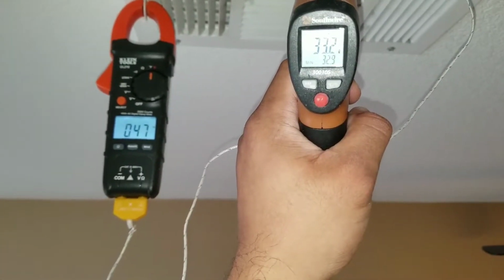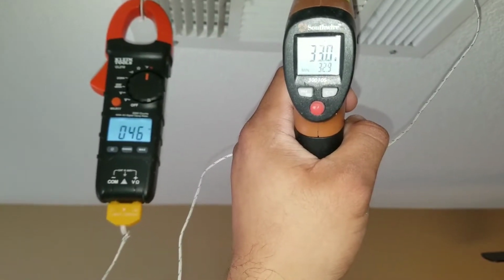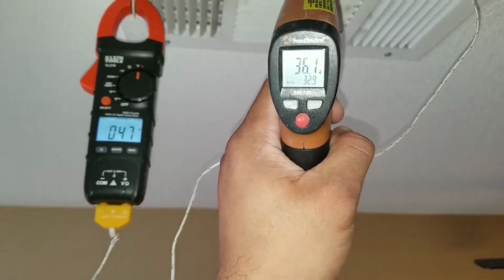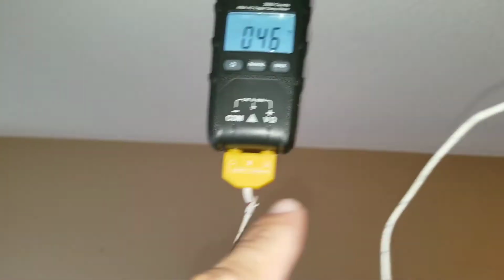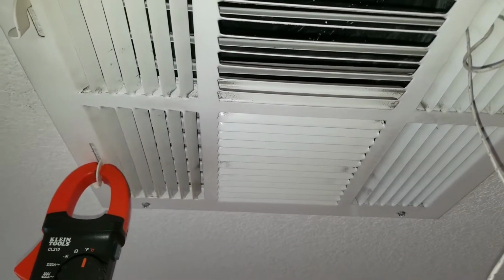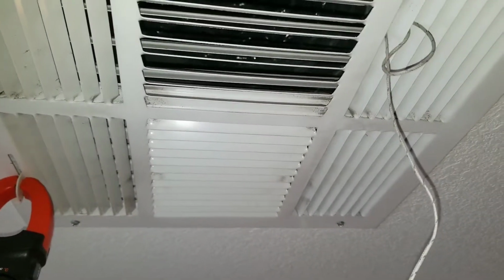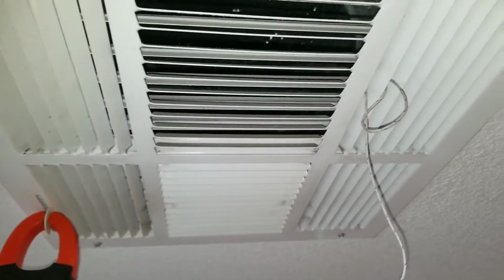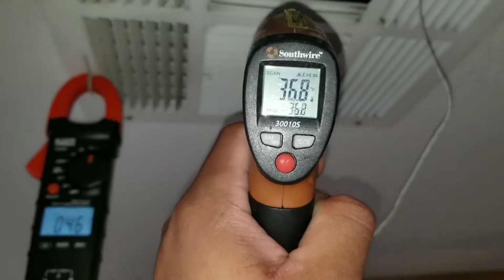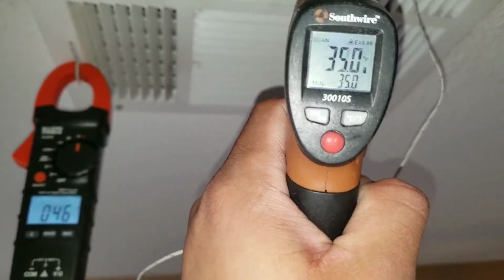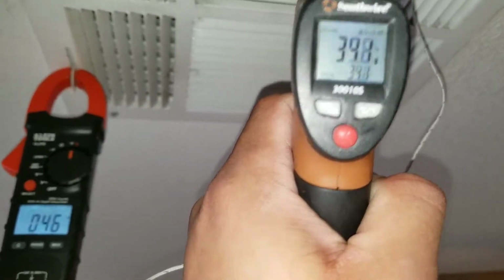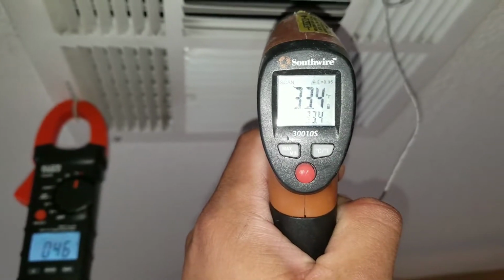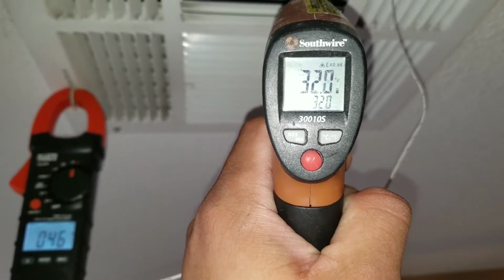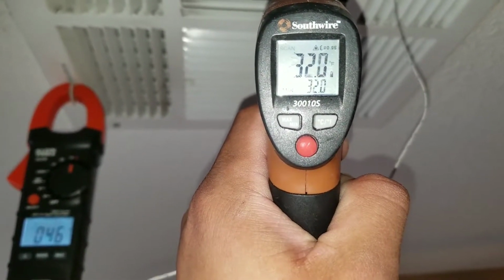When you're dealing with heat or HVAC calls, you're going to want to use the multimeter method. Reason being is because your multimeter has a temp probe. The temp probe is actually giving you the reading of the ambient, or rather here in this case, the temperature of the air that's coming out of the vents. Whereas the temp gun is giving you a reading of what the surface is that the laser is actually touching. What I mean by that is my temperature coming out of this vent is not 33 degrees. The vent itself is 32 degrees right now.